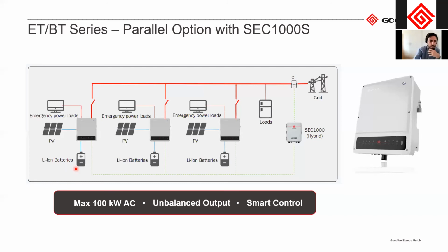So then there's no possibility, if, let's say, the battery from this one is dead and there's no PV here, that the emergency loads connected to this inverter can be supplied by the second inverter, even if this one has additional battery and PV power. So it's important to know that when the grid is on, they can all operate together, but when the grid is off, they will be seen as isolated systems.